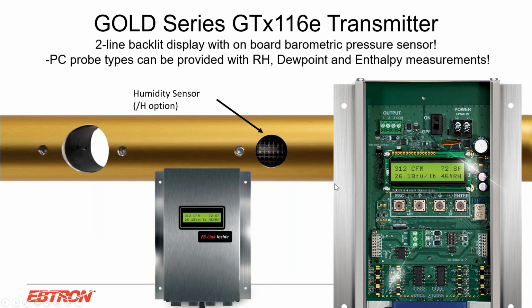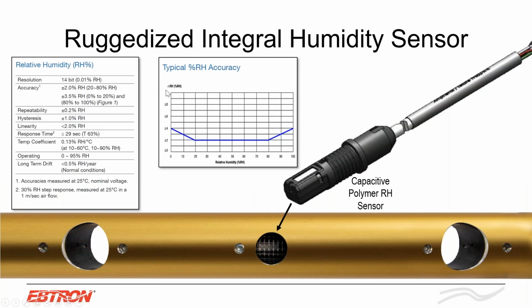Now, something that we've come out with, and it's really revolutionary, and I'm going to talk about that because of how we're calculating it, but with our Gold Series units, for duct or for your outside air intakes, we now have the option for relative humidity measurement. And this can read relative humidity, dew point, or enthalpy, right? So this is the ruggedized integral capacitive relative humidity sensor we use. We put this on the discharge side of the probe to make sure it doesn't build up with anything that's coming in from your outside air intake. And it's a plus or minus 2% relative humidity reading over the normal operating ranges, right?